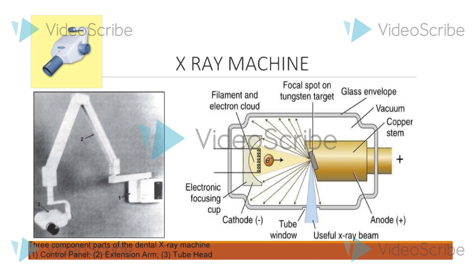The filament is the source of electrons within the X-ray tube which is made up of tungsten wire about 2 mm in diameter and 1 cm length mounted on two stiff wires. It is heated by the flow of current from the low voltage source and emits electrons.